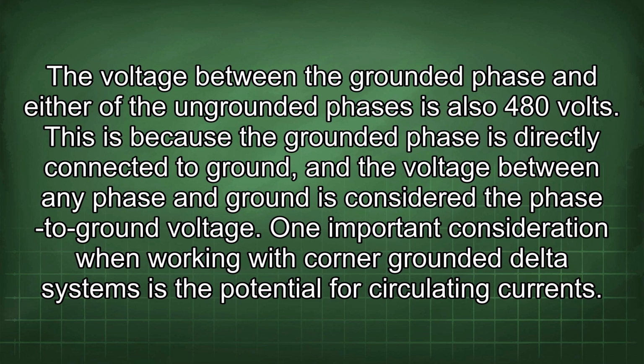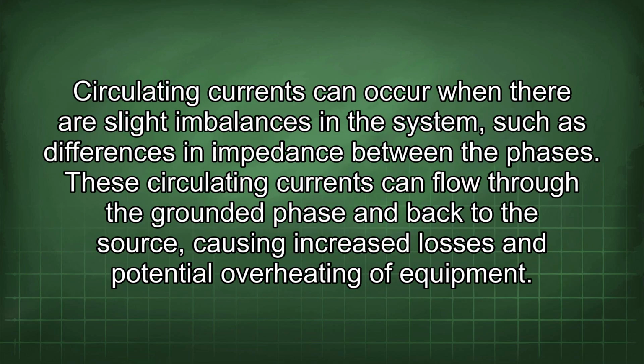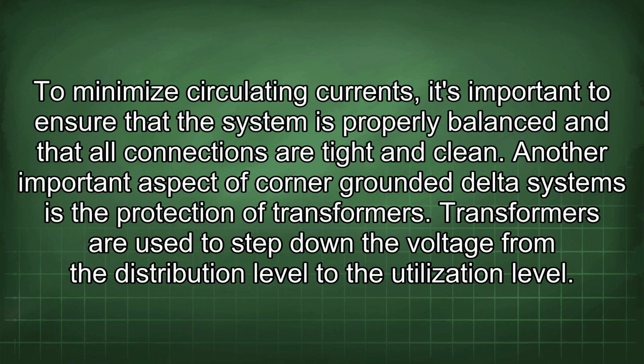considered the phase-to-ground voltage. One important consideration when working with corner-grounded delta systems is the potential for circulating currents. Circulating currents can occur when there are slight imbalances in the system, such as differences in impedance between the phases. These circulating currents can flow through the grounded phase and back to the source, causing increased losses and potential overheating of equipment.